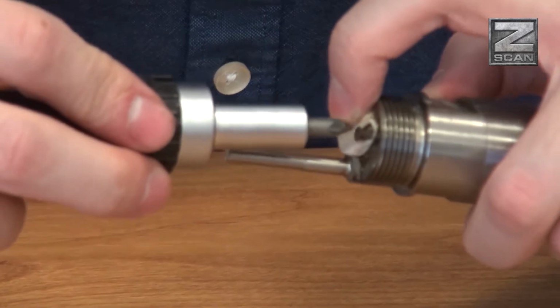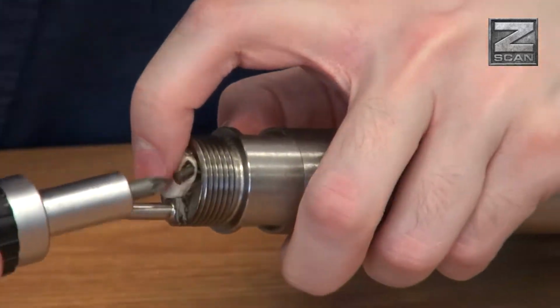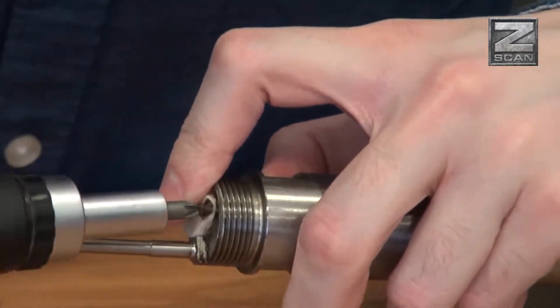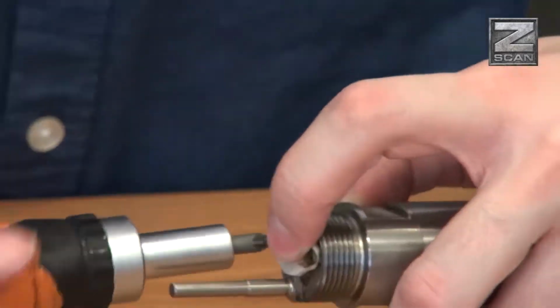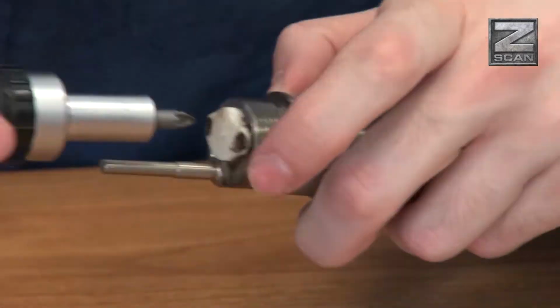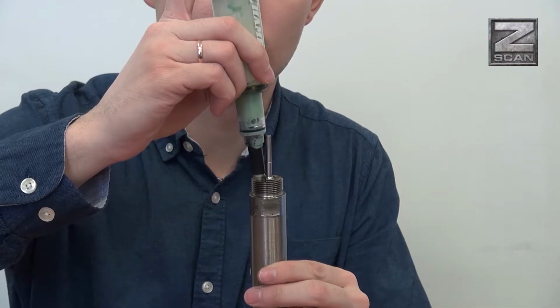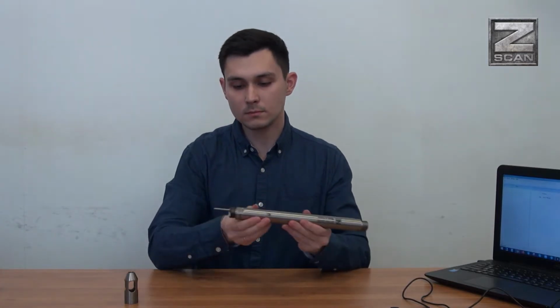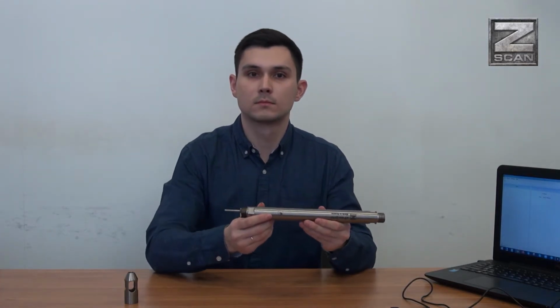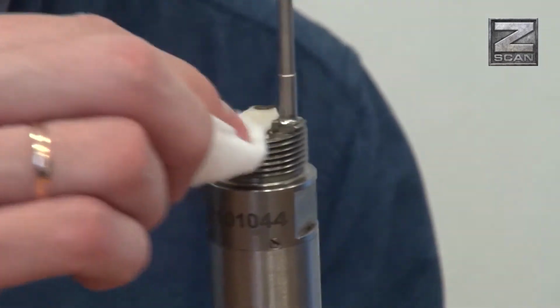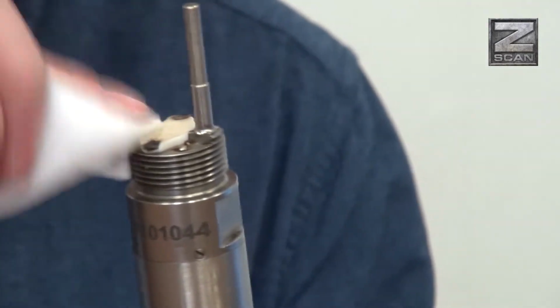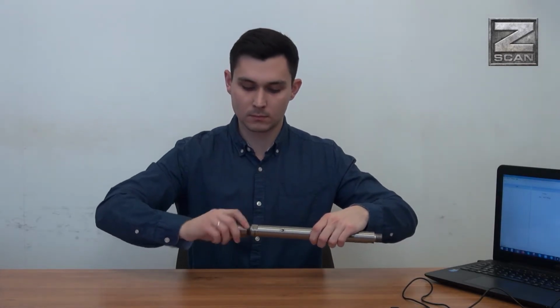Refit the plug using the fixing screws. Apply lubricant using the lubricant nipple in the lubricant change channel until it exceeds the hole on the plug. Care should be taken to avoid damaging the plug. Remove excess lubricant with a rag. Attach the bell nose to the sensor assembly.